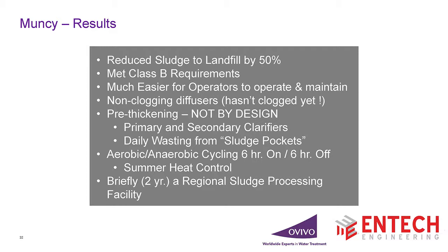They continued that cycle for 13 years. It gave the operator 6 hours of settling time to take some decant, thicken in the digesters, controlled the temperatures, and we had these excellent results. That's not only excellent results for denitrification, but it was excellent energy performance also.